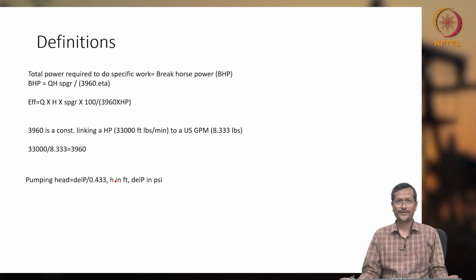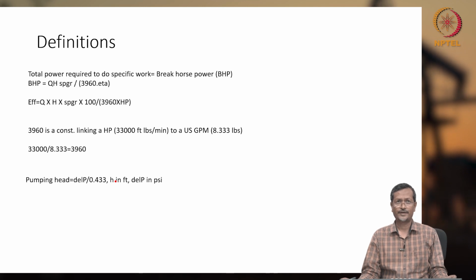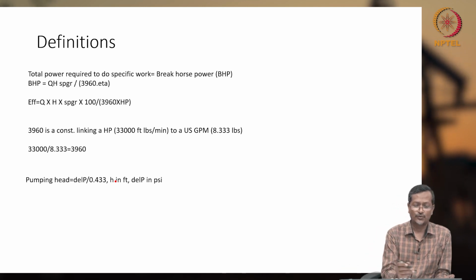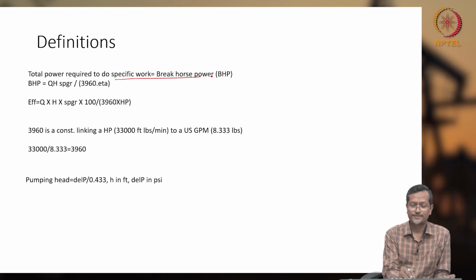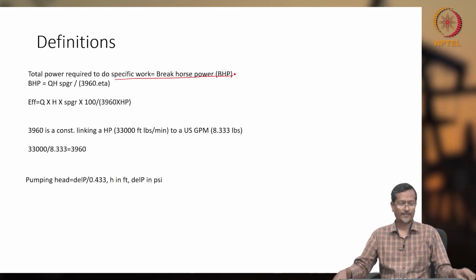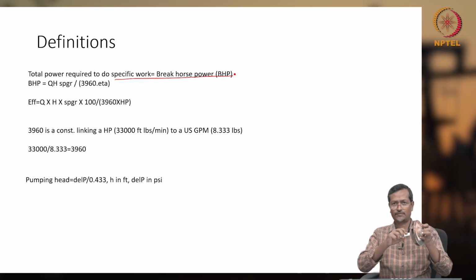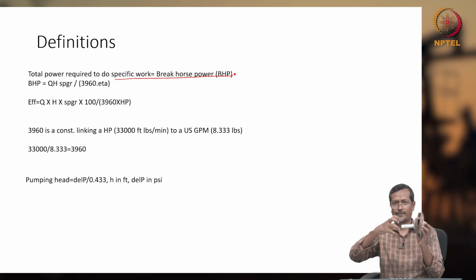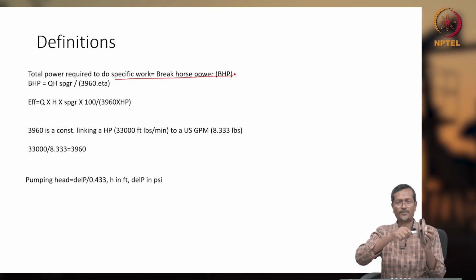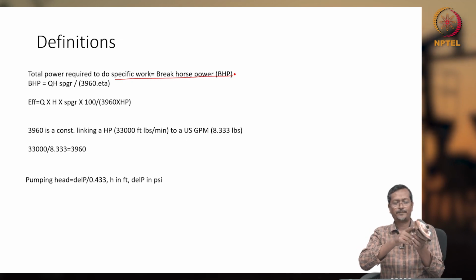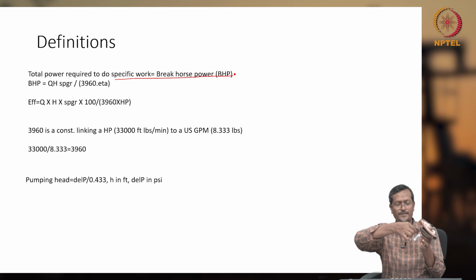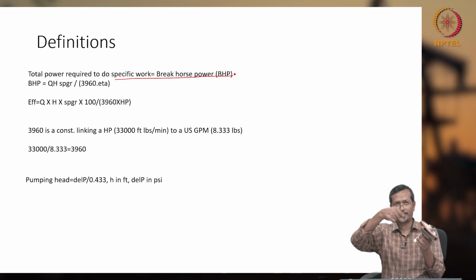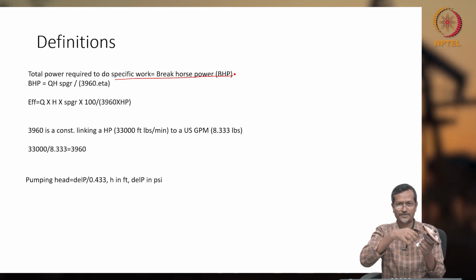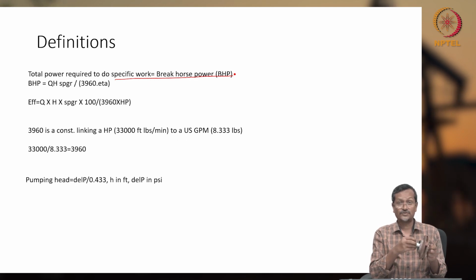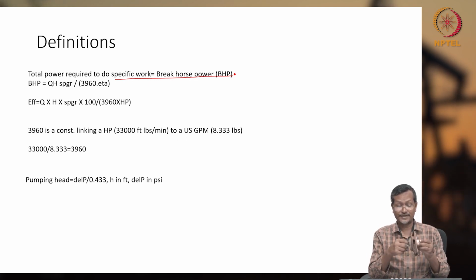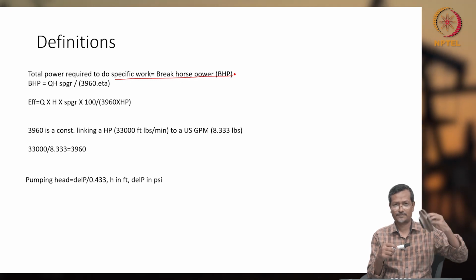Okay. So, whenever we discuss ESP, we should define certain parameters. So, total power required to do specific work, brake horsepower. Brake horsepower means this shaft is connected to this one, okay, motor is here, okay. So to measure how much power it is taking, what we'll do is put some brake here, and we'll measure how much energy it is showing, how much energy is getting lost to stop this motor, okay. So that is called brake horsepower. So how much total energy is used by this impeller or this machine, okay.